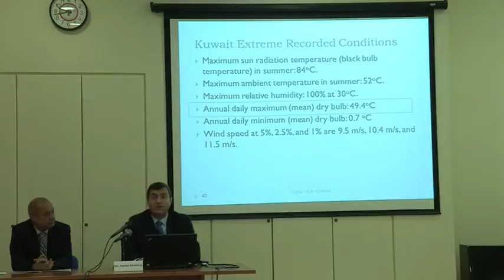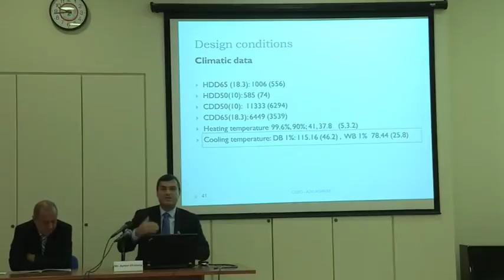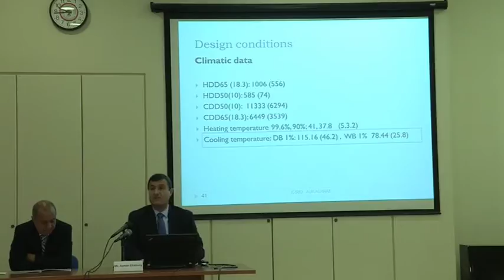The cooling degree days, for example, is 11,500, something in that range. So ASHRAE puts values at 9,000, but here in Kuwait it is a lot more than 9,000. The design cooling temperature is 46 according to ASHRAE's criteria, dry bulb 1%, as those who are doing cooling loads know what I'm talking about. So the design condition is 46. And in every country there is confusion about why 46, why not go higher. Policy makers who are not really in the business of air conditioning and design say, let's set the design conditions higher because the temperature goes above 50. But when you bring the design condition 1 degree up, the cooling load goes much higher, meaning you need more energy. So this is a very important point we should be aware of when we address the policy maker.